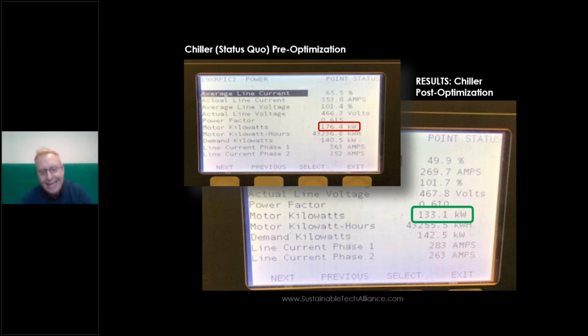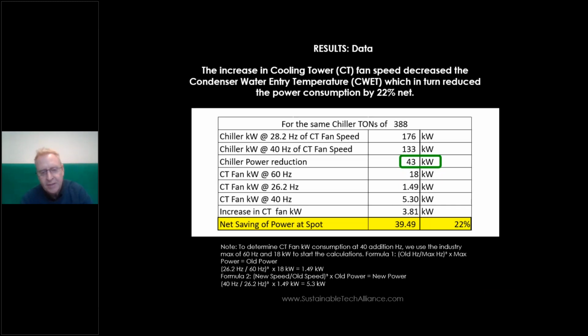And the way the math worked out is the cost for the increased fan was 3.81 kW. So in a dollar sense, we were spending about $3.81, 38 cents, right? 3.81 kW at the 10 cents saved $4.30. So you subtract the added cost of the energy from the gain, the benefit, and you end up spending about 40 cents to save $4 every hour of every day. With 8,760 hours in a year, that small measure, pushing that one button, saved over $32,000. Now, some of the buildings we've worked with can save well over $100,000. In this example, the micro change compounded to what would be over time a significant impact.